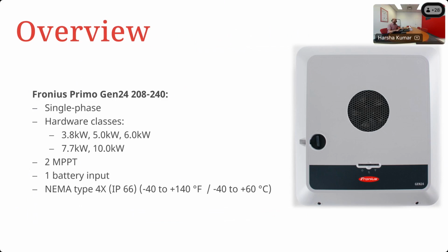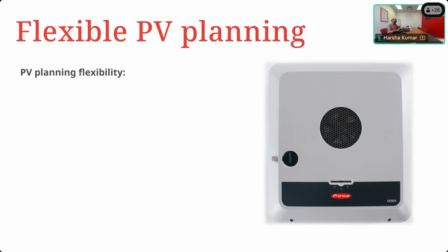Now, in terms of PV planning flexibility, the start voltage is 80 volts. But that doesn't mean you should be working an inverter at that low voltage, because you have to remember that the inverter is an electronic device and all electronic devices are current limited. So what I mean by that is the amount of current that the inverter can handle is fixed. There's a maximum to it. But from the calculation for power, we know power is voltage times current.